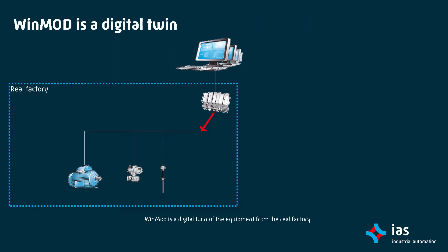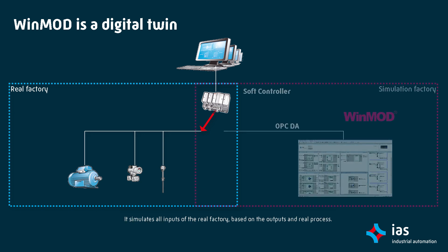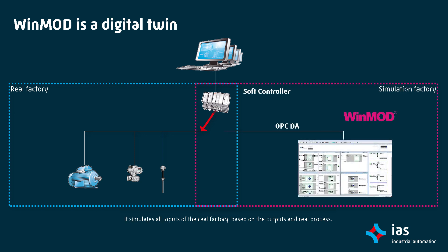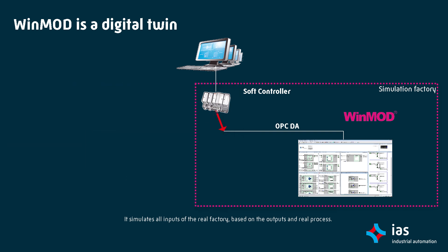WinMod is a digital twin of the equipment from the real factory. It simulates all inputs of the real factory based on the outputs and real process. All simulated I/O values are written to a soft controller through OPC DA.